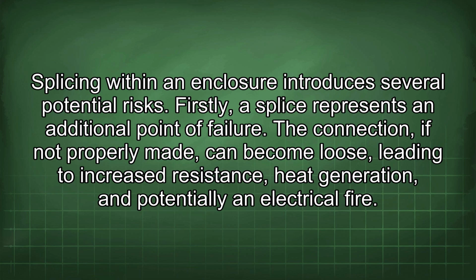Splicing within an enclosure introduces several potential risks. Firstly, a splice represents an additional point of failure. The connection, if not properly made, can become loose, leading to increased resistance, heat generation, and potentially an electrical fire.